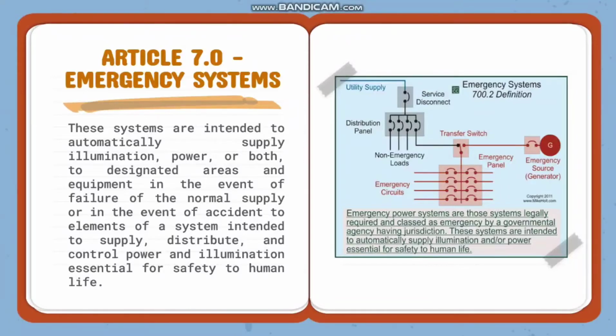This system is at the top of the hierarchy of backup power systems in terms of their level of importance. Basically, their level of importance corresponds to the order in which they appear in the PEC. So this is the single line diagram for emergency systems. Moreover, emergency power systems are those systems legally required and classed as emergency by a governmental agency having jurisdiction. These systems are intended to automatically supply illumination and/or power essential for safety to human life.